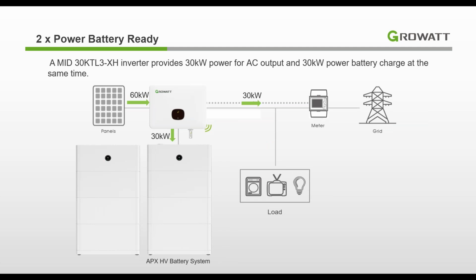Here is the Mid 30 kilowatt XH, quite similar to the Mod. For a 30 kilowatt inverter, you can have 60 kilowatt from your panels, with 30 kilowatt charging the battery and 30 kilowatt feeding the load. Since it's a 0.5C battery, to reach 30 kilowatt charge discharge you'll need 60 kilowatt hour battery at least. The difference here is the Mid has 2 battery ports, supporting two stacks of APX. One stack is up to 30, so two stacks of APX is 60 kilowatt hour total, meaning you'll need 12 batteries at least to achieve the 30 kilowatt charge discharge rate from the battery.